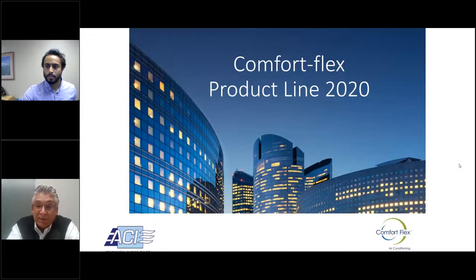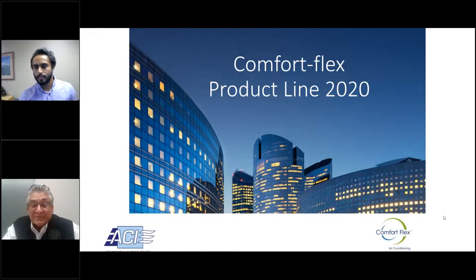It's very similar to a cooling tower, right? So the media in this case is the deck, the media deck. It actually has a sump and a pump as well to recirculate that water across that media. So water treatment and cycle rates are also a concern when you're looking to apply that product. Great question. Yes. It's like a mini cooling tower, if you think of it that way, with a pump assembly and a sump, and cycle rates and water treatment pretty much the same. Yeah, exactly. Filtration can also be added, which helps remedy some of that concern with water treatment, separators and those kinds of things, right? We can put in an onboard pump package as well to help assist with that, or custom.